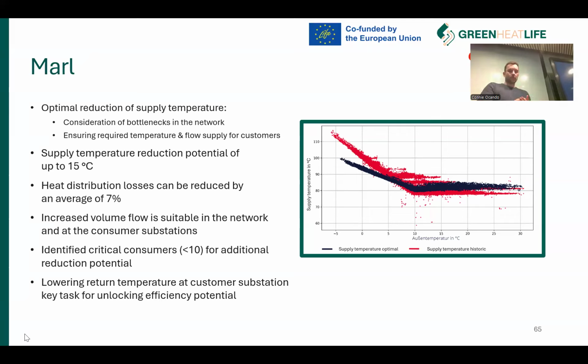So in summer, during high outside temperatures, we have quite high return temperatures in the network. The digital twin shows us we should also have a little bit higher supply temperatures than historically, and therefore the volume flows in the network will decrease, saving some pump energy. This is the optimized supply temperature during high outside temperatures, recommended by the digital twin for optimal pump energy and operation. The return temperatures are quite high in Marl, and therefore higher supply temperatures are recommended.